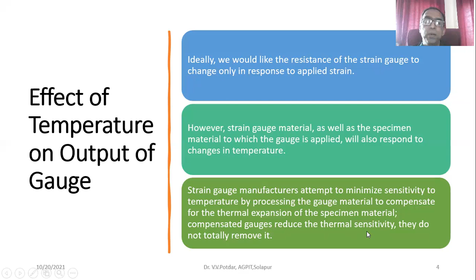Let us quickly see the slide. Ideally, we would like the resistance of the strain gauge to change only in response to applied strain. However, strain gauge material as well as the specimen material will also respond to changes in temperature. Strain gauge manufacturers attempt to minimize sensitivity to temperature by processing the gauge material to compensate for thermal expansion of the specimen material. Compensated gauges reduce thermal sensitivity, they do not totally remove it, but provide temperature compensation.